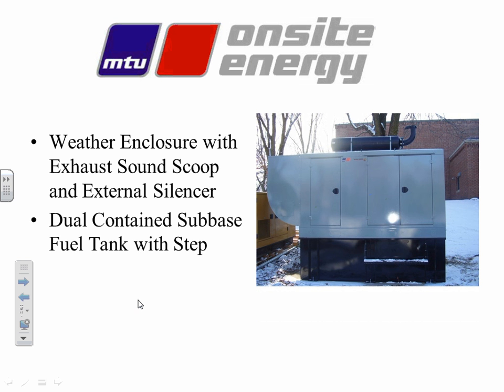Here's a little different design. If you remember, I talked a little bit about sound attenuation in an earlier slide. This is another type of sound attenuation. It's just minimal. It's a step above the weather enclosure, so we call it the weather enclosure with the exhaust sound scoop. That's this part here. The other one I showed you just finished off the whole thing, and you had a longer tank, and it was more aesthetically pleasing, but we'll save a little sheet metal by doing it this way, and just use the up duct, direct the air up. That's going to reduce the noise, because noise travels in a straight line. So this is a little bit of sound attenuation.